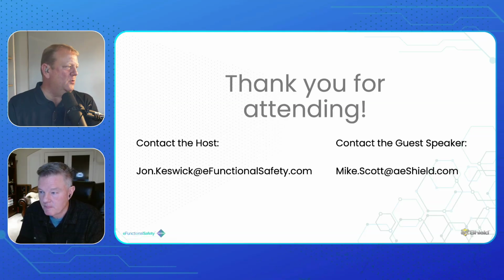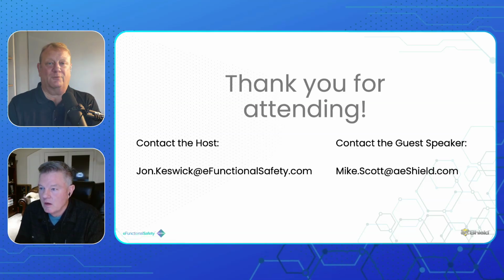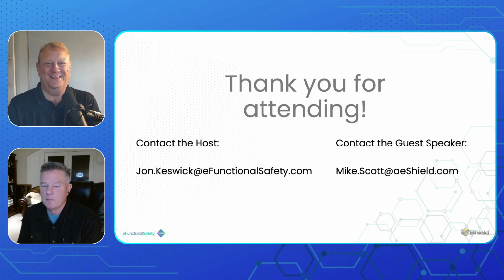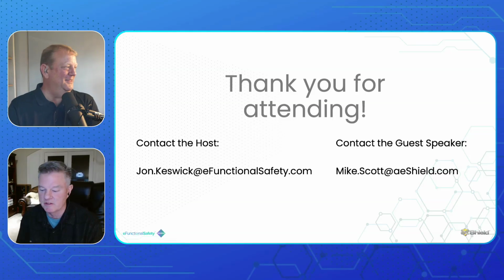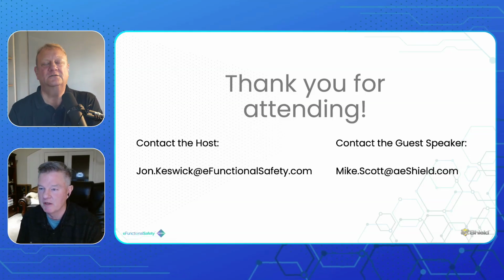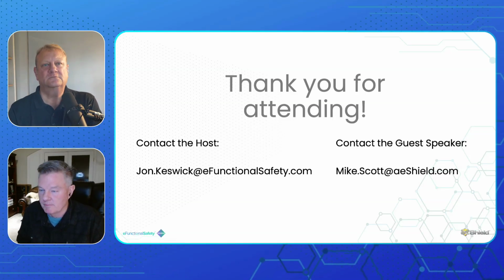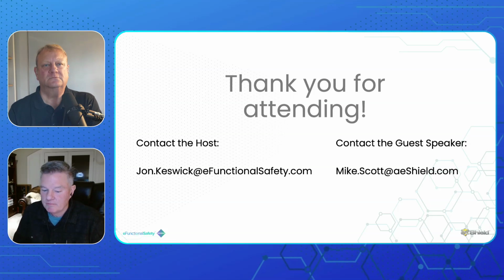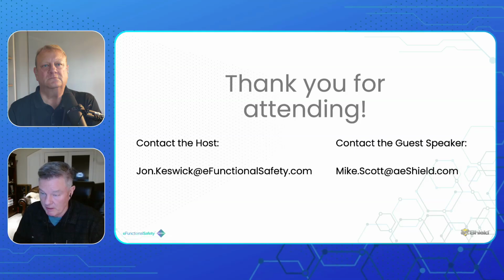The second one is from Scott Abraham. Pros and cons of Bayesian versus Gaussian calculations. I'll leave that one to you, Mike. So Bayesian works really well for limited data sets. I'd highly recommend you go after the Bayesian when you're first starting out. If you have 15 years worth of failure rate data, the Bayesian and Gaussian are going to give you the same numbers, so it won't really matter.